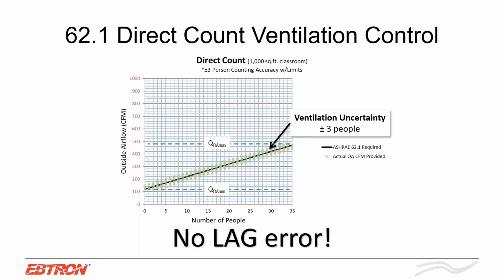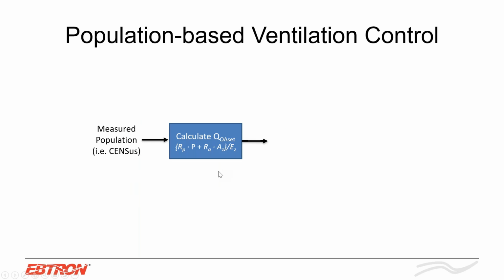If you have a huge gymnasium, well, it might take a long time for that CO2 sensor to reach the production rate of 1,000 parts per million to actually start ventilating the space. And again, you have a 20-minute lag on top of that. On the back end, when people leave the space, there's still that 20-minute lag. So a lot of times you will be ventilating the space based on 1,000 parts per million where you have no occupants in the space. So that's also another issue with the CO2 sensor. This is, again, the control logic if you are using, for example, the EBTRON product, the census, and measuring the population.